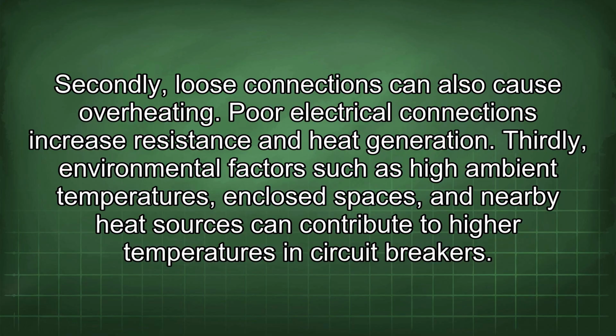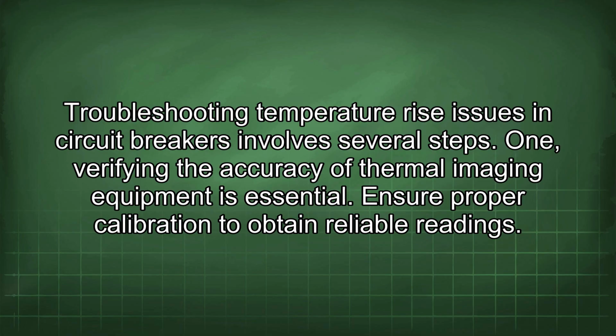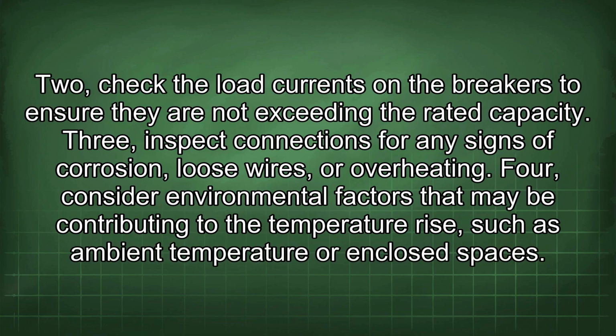circuit breakers. Troubleshooting temperature rise issues in circuit breakers involves several steps. 1. Verifying the accuracy of thermal imaging equipment is essential. Ensure proper calibration to obtain reliable readings. 2. Check the load currents on the breakers to ensure they are not exceeding the rated capacity.